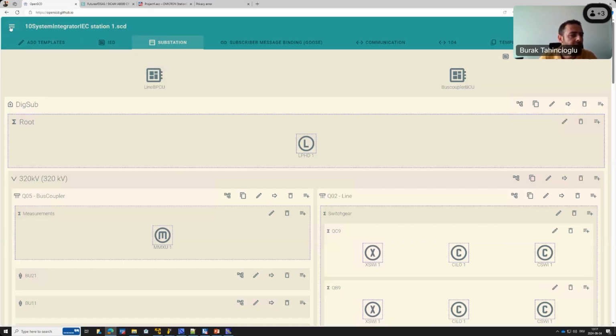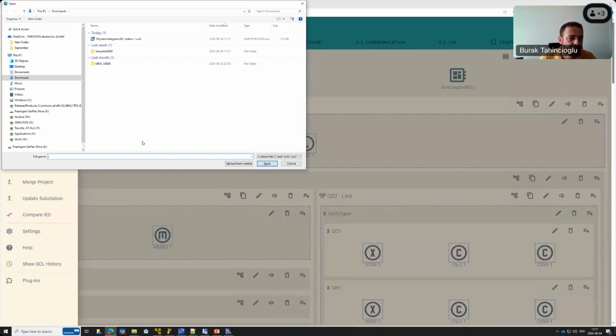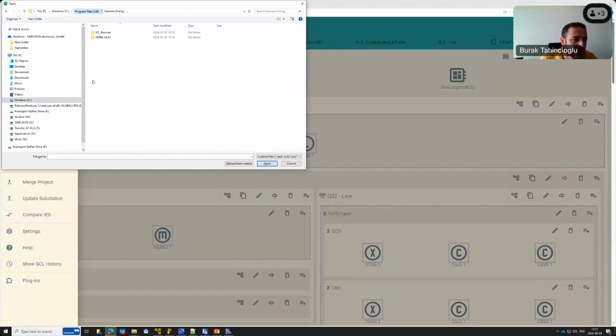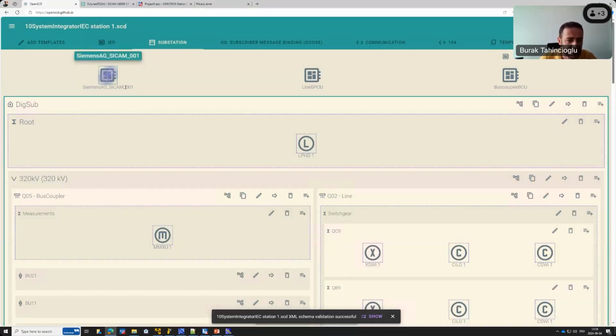I will add another IED to have this client, and add another client. I'll use the Siemens offered clients since I have a Siemens IED with me—you can find it here. In Siemens System Configurator, in the ICD path, you have these dummy clients. I want the ICD file of the client, added to the client, and open it up—then the Siemens SICAM client shows up here.